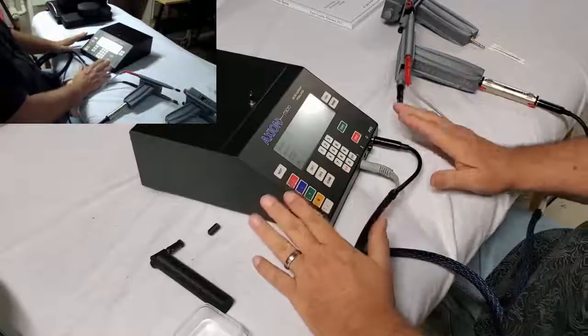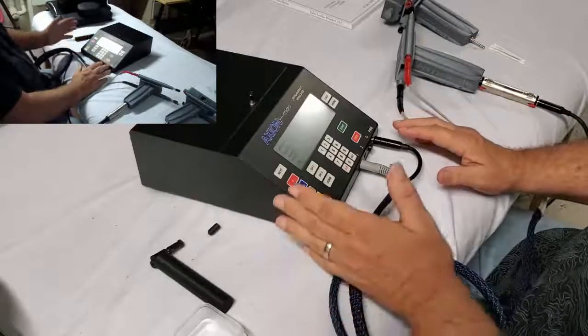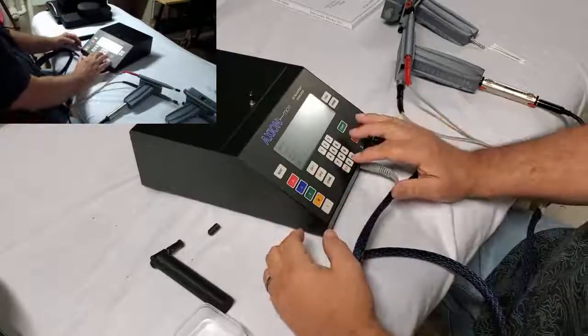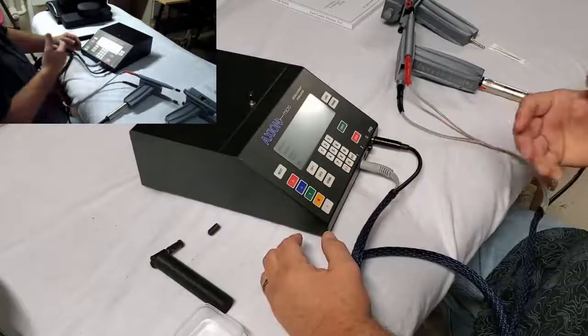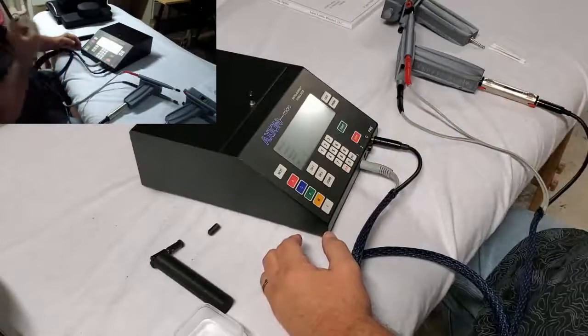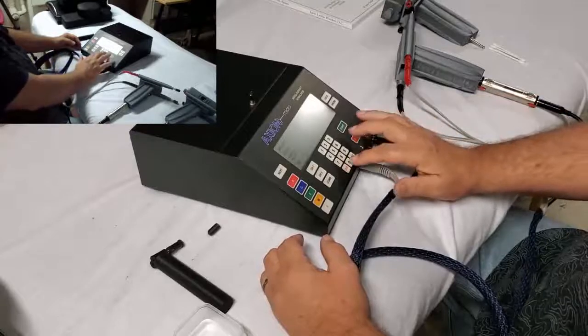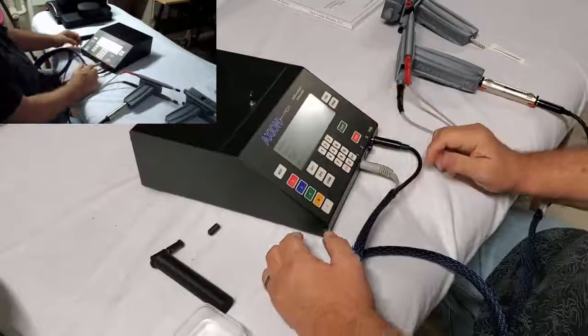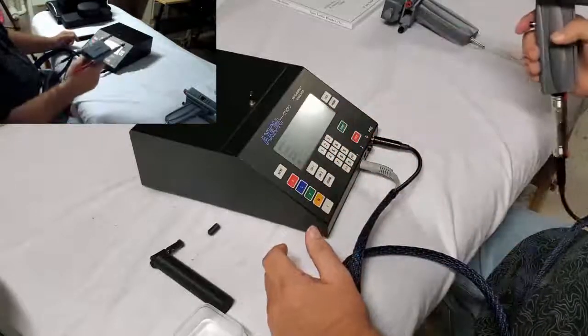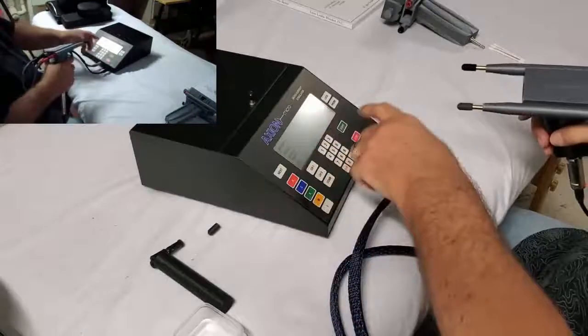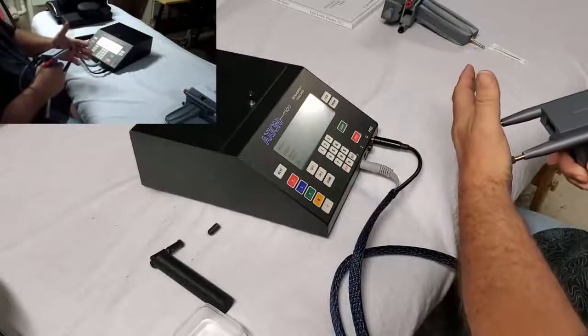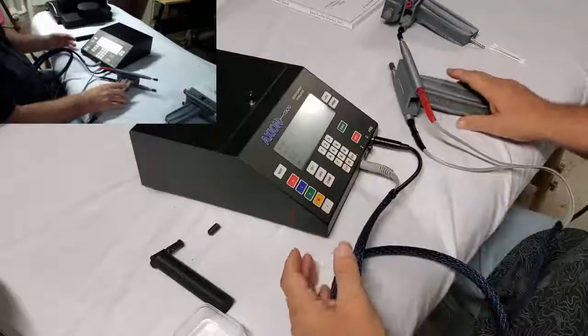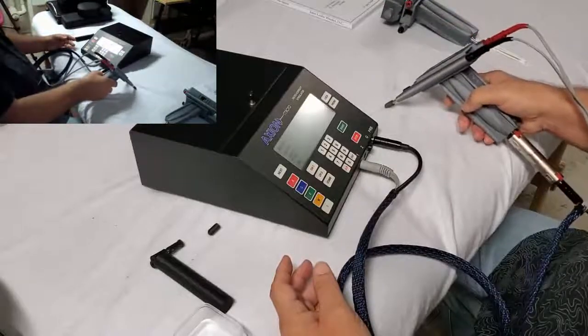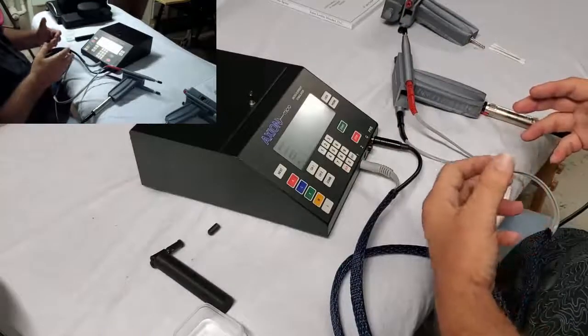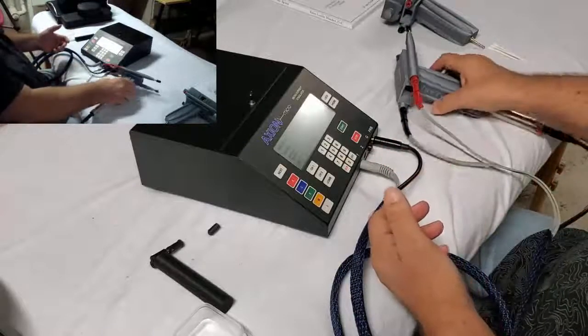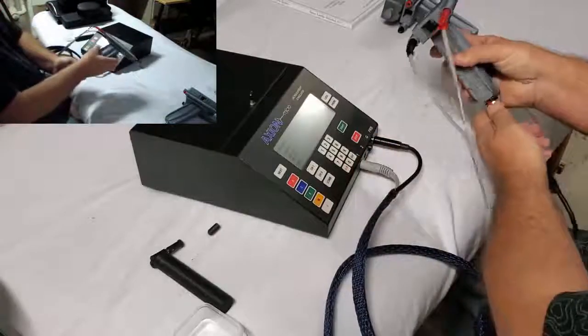One of the things in the new update is the ability to change the frequency to 2 digits to the right of the decimal point. So for example, if I wanted to deliver the Earth's frequency, the grounding frequency, also known as the Schumann's resonance, I can set the frequency to 7.83. And when I press the button, that's exactly what will be delivered through these 2 tips. So we can use this to fine-tune the current that we want to send through any part of the body, but in particular with this new gun through the spine, and deliver that harmonic that that particular spinal segment will react to. So that's gun number 1.